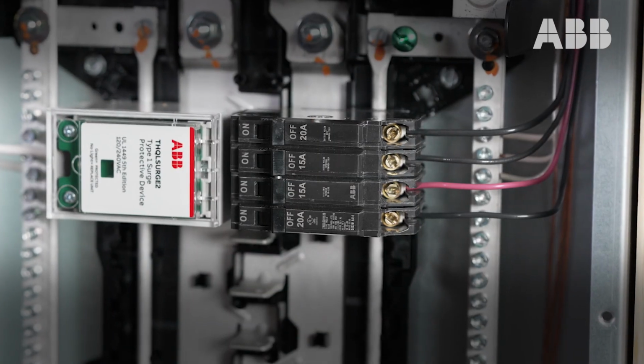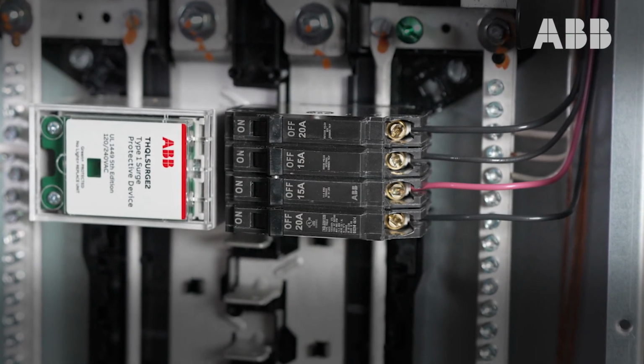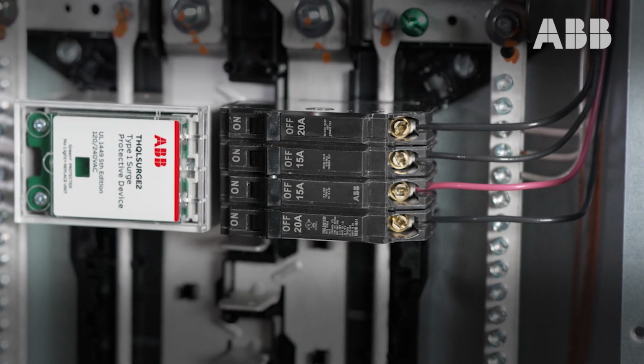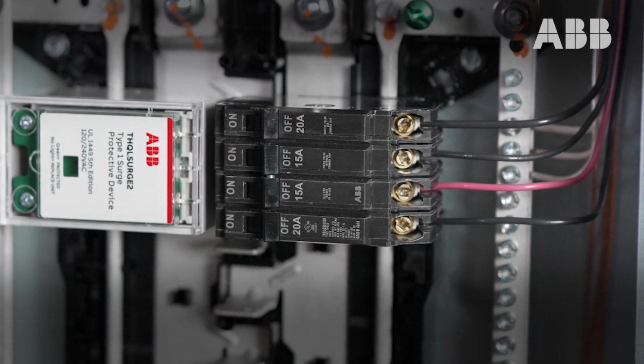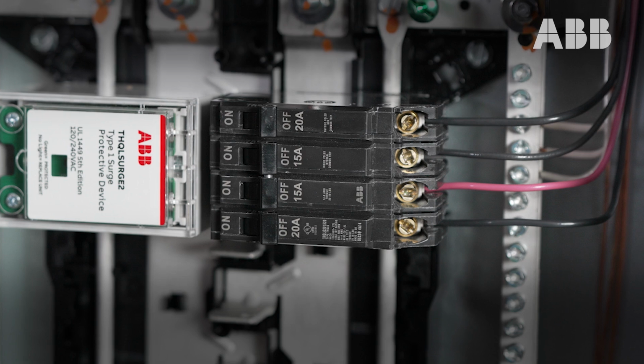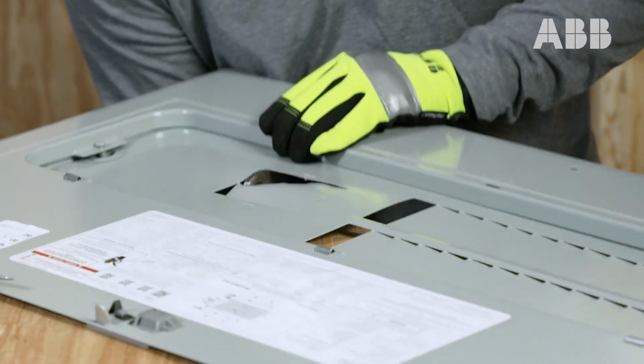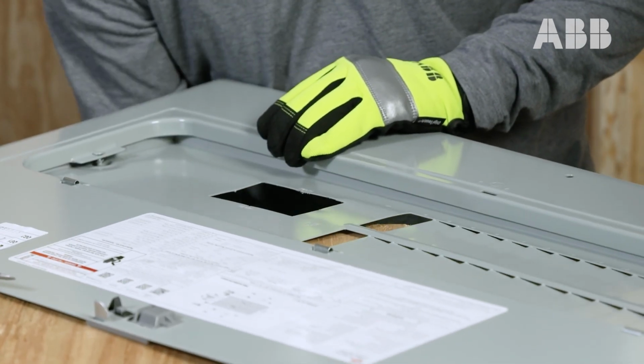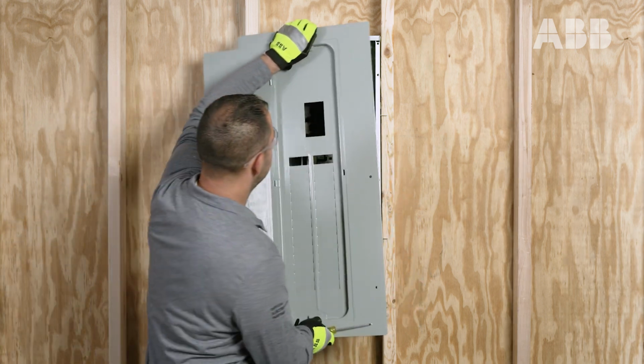For quad circuit breakers, repeat this step for each single pole lug. Then wire 2 pole lugs by connecting one red wire to one lug and one black wire to the other lug. Remove the necessary circuit perforations from the cover, then reinstall it onto the load center.